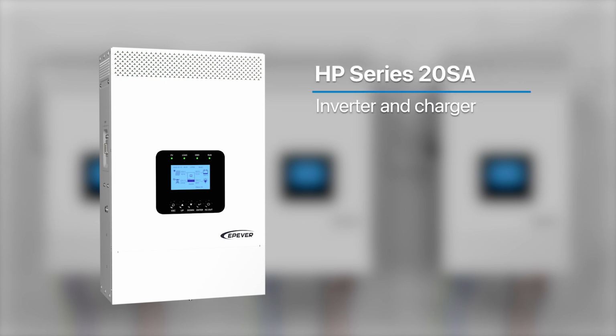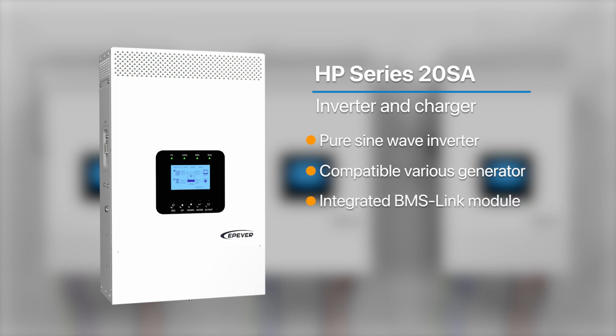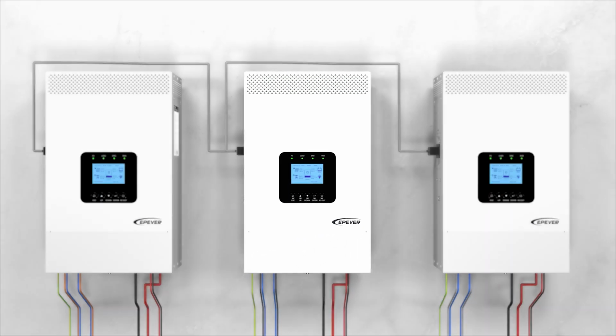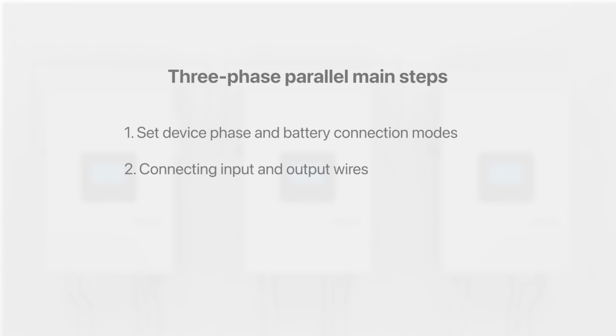The HP Series 20SA is a cutting-edge inverter charger featuring pure sine wave output, compatible with various generator types for charging. It includes an integrated BMS link module and a historical data record function. This device is capable of managing multiple energy sources and supports both single-phase and three-phase parallel output in a fully digitalized format. In the following segment, we'll guide you through the phase setting process for the device and demonstrate how to establish a three-phase connection. Topics covered include: set device phase and battery connection modes, connecting input and output wires, linking parallel communication lines.